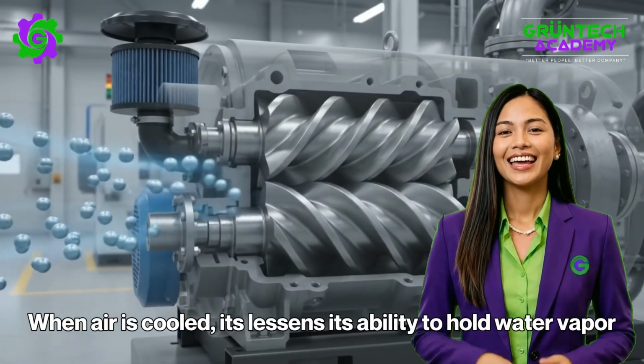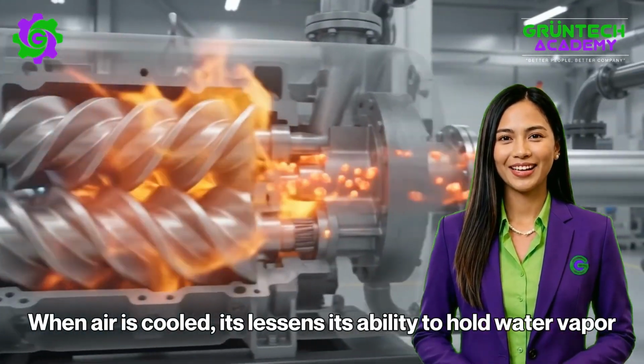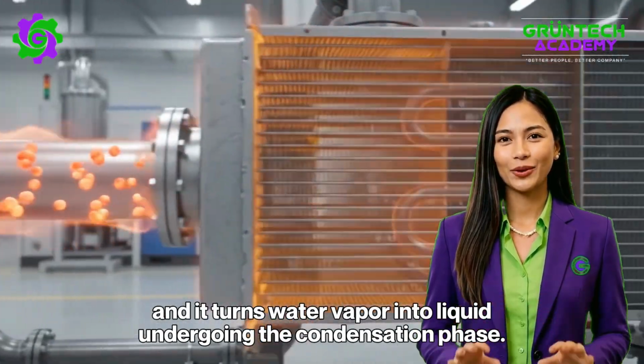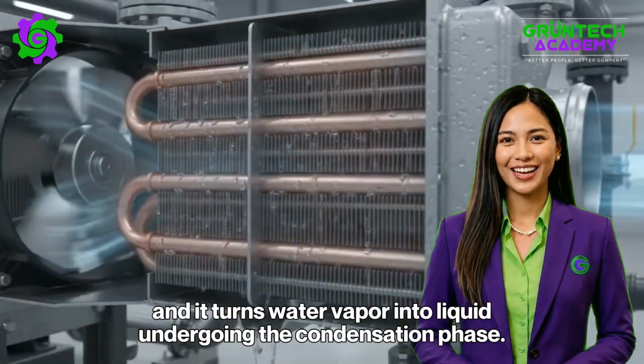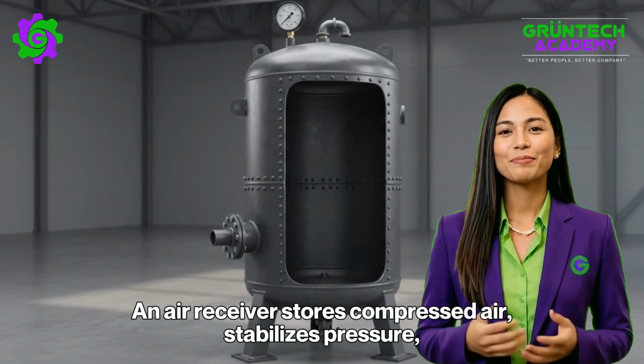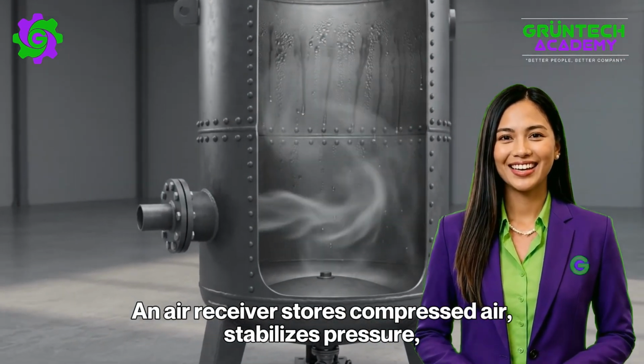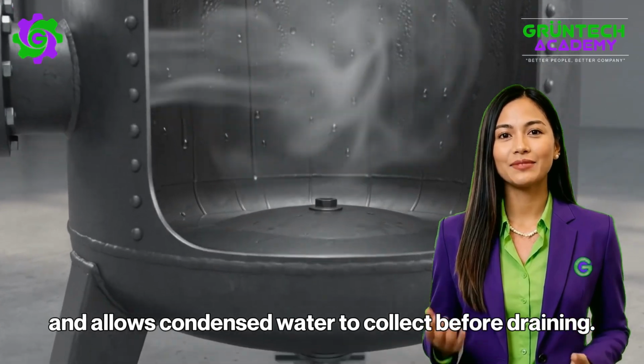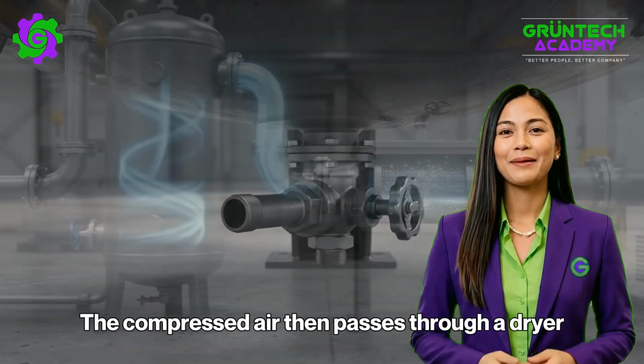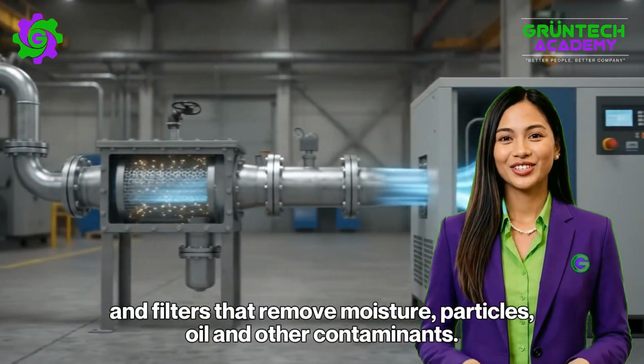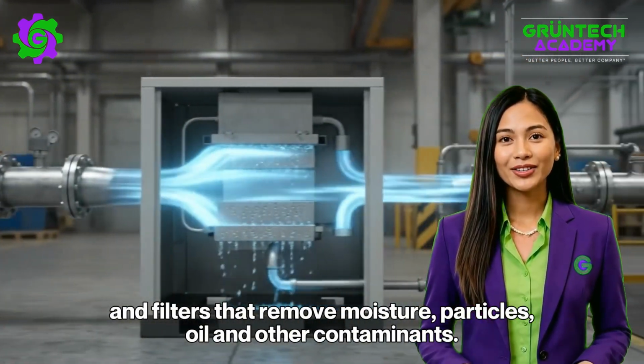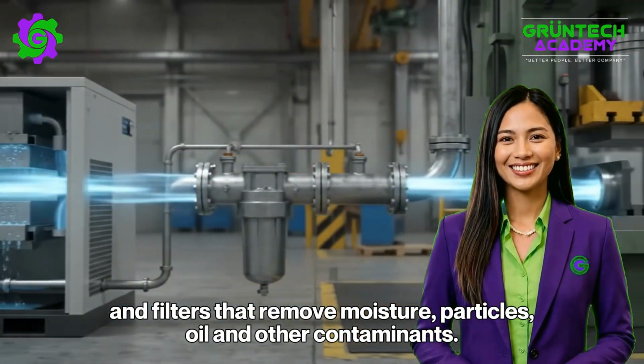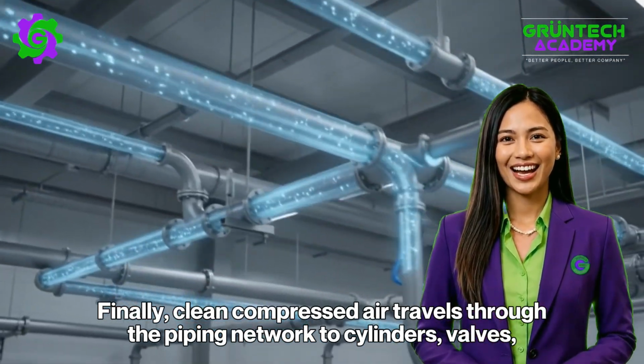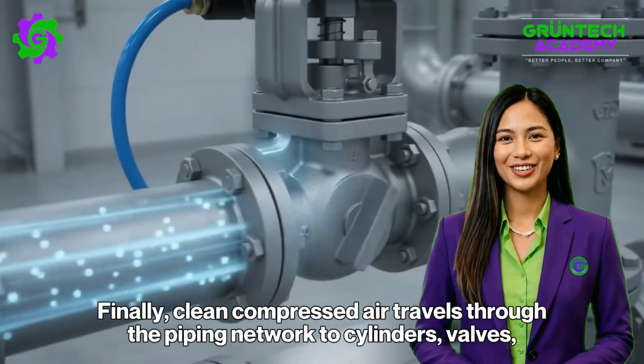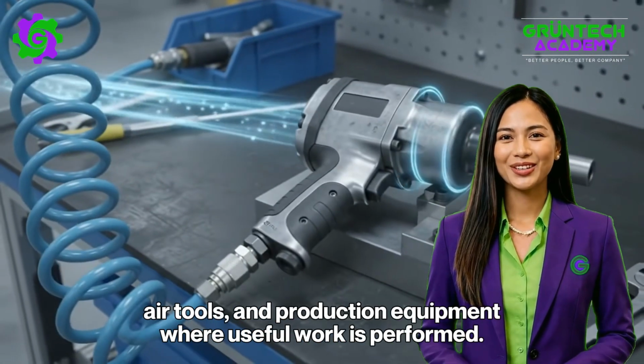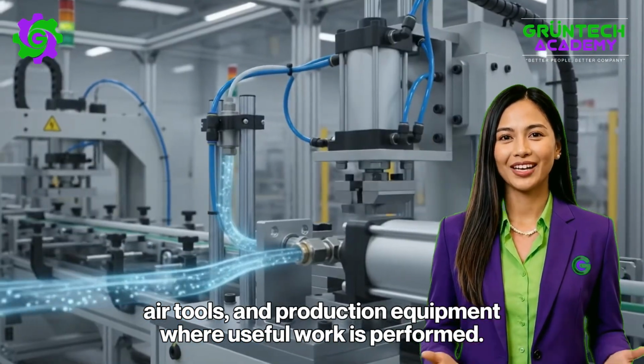When air is cooled, it lessens its ability to hold water vapor, and it turns water vapor into liquid, undergoing the condensation phase. An air receiver stores compressed air, stabilizes pressure, and allows condensed water to collect before draining. The compressed air then passes through a dryer and filters that remove moisture, particles, oil, and other contaminants. Finally, clean compressed air travels through the piping network to cylinders, valves, air tools, and production equipment where useful work is performed.